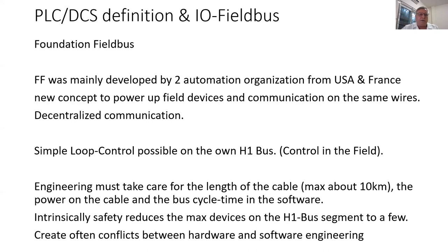So the concept with the remote cabinets is much better, much easier to handle than this Foundation Fieldbus. I'm not really a friend of Foundation Fieldbus, and all the devices and everything else are much more expensive than the other ones. They say you can save engineering time, which is not really true, as I told before, if you don't work together well enough. And even in the loop check and commissioning time, that should be so easy, but it is not so either.